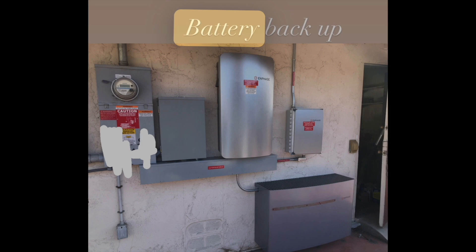There's actually a fifth component too — the critical loads panel and transfer switch for full off-grid capability. Something I've seen recently is that to cut costs, companies are quoting batteries but not including the critical loads panel or transfer switch, which means if the grid goes out, your battery won't work like you expected. That's often a five to six thousand dollar difference.